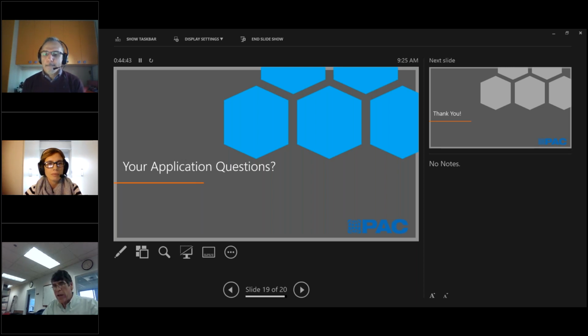Yeah, so I'll quickly answer the calibration question first. We recommend performing a calibration check once per year. What that entails is removing the sensor from the system, cleaning it, adding a calibration fluid, and running it to ensure that the viscosity reading is within 1% of the calibration fluid value. So these hold their calibration for a very long time. There are other types of viscometers out there, such as torsional or vibrational, which need to be checked much more frequently, as you know, since the process conditions do affect their calibration. But it's a very simple process to do.